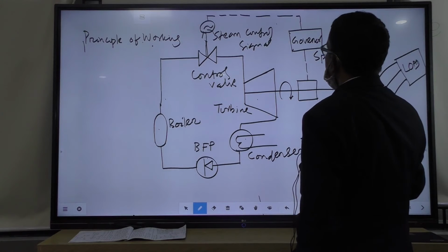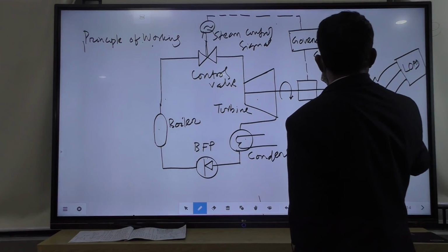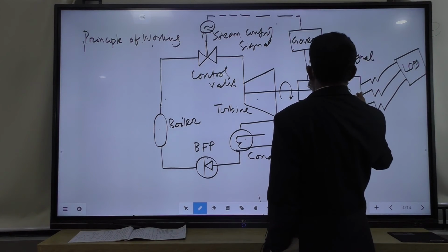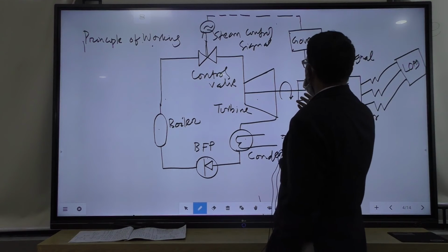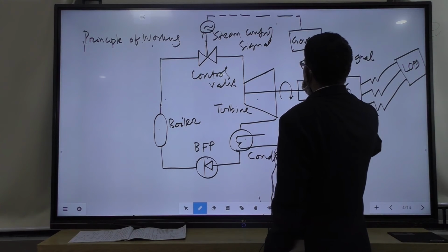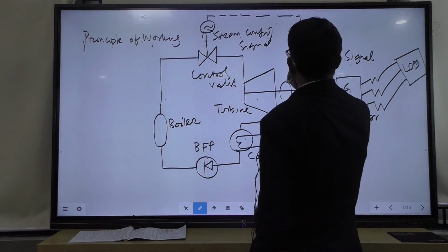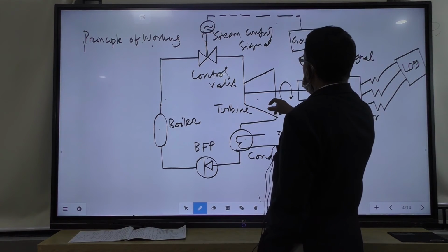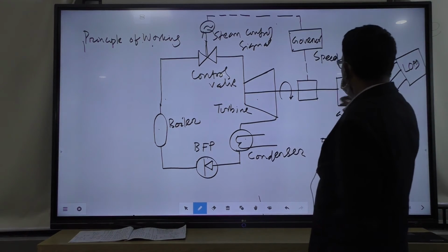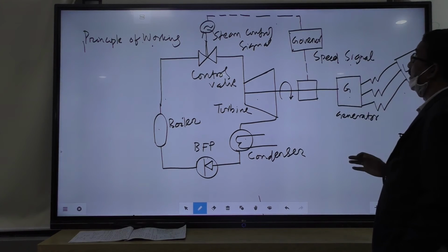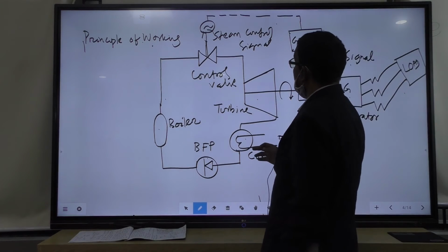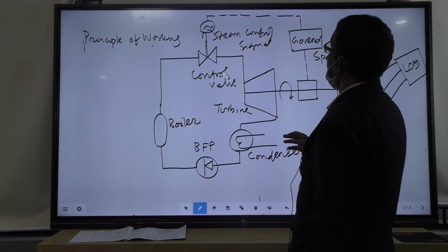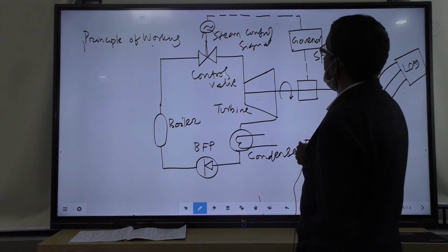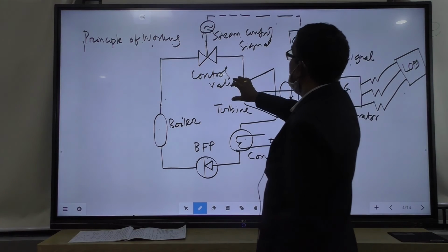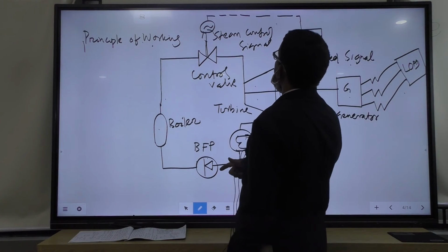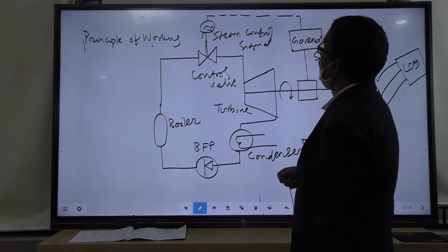If the speed increases too much, the turbine shaft may bend because there is no necessity of running at a high speed without consumption of load. If the turbine rotates and there is no consumption of electricity, there will be imbalance between the load and input and output. The input is your turbine power to the generator, and the output is the electricity. If input and output vary, at that time the turbine rotor may bend or the shaft may be damaged. So therefore the governor will take the governing action by allowing less quantity of steam to the turbine at that time. So this is the principle of working of the governor.